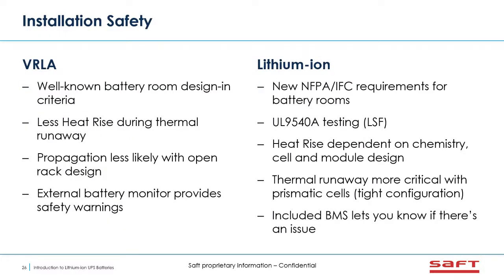Installation safety. So VRLA batteries have very well-known battery room design criteria. I would say the heat rise during a thermal runaway is less. The likelihood of propagation on an open rack design is a lot less. And then with the addition of a battery monitoring system, it definitely improves, let's say, safety overall. And then if we look at some of the new requirements for lithium-ion batteries, NFPA and IFC have new requirements for battery rooms. So these are pretty well documented now in the latest codes from 2018 and on. They do require now a lot of additional testing, and one of the tests I mentioned here is UL 9540A, which is a large-scale fire test. And that's an evaluation of the system. Again, we'll probably talk more about that in the safety presentation.